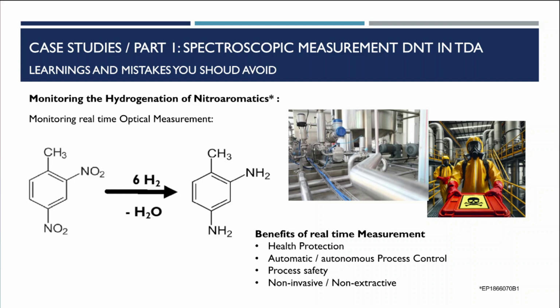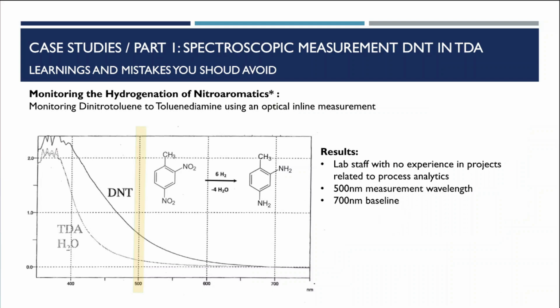It's an important point, again, to test the ideas you have before you buy everything right away, only to find out it doesn't work. Check the process conditions, if possible, before you make the final decision for measurement. So it takes a long time to make these tests before you think about installing it in the process. Here you can see the picture of a spectrum recorded with a spectrometer. It was found that the wavelength of 500 nanometers represents the concentration of the DNT, and it was quite good to see the 200 ppm. At 700 nanometers is a good baseline.